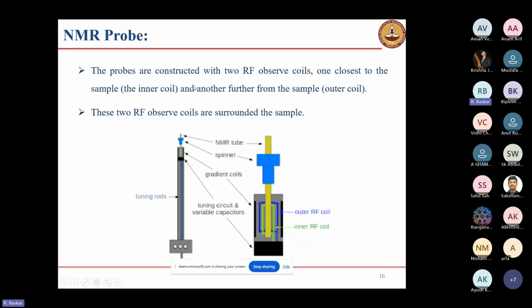The probes are constructed with two radio frequency observe coils. One is close to the sample, that is the inner coil, and the second is next to the inner coil, that is the outer coil. These two radio frequency coils surround the sample. Here in the image we can see the inner radio frequency coil, and next the outer radio frequency coil. This is the NMR tube. This is the spinner. These are the gradients, which support shimming. Down here we can see the tuning rods, the radio frequency tuning rods.